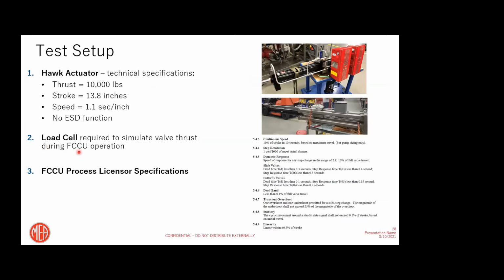So we didn't test only the actuator. We actually created a load cell, which simulates the thrust load of the valve, and we connected our actuator to this load cell. Additionally, we took the FCCU process licensor specifications, and we were more familiar with the UOP specs. So we took one and started testing our unit to those current standards.